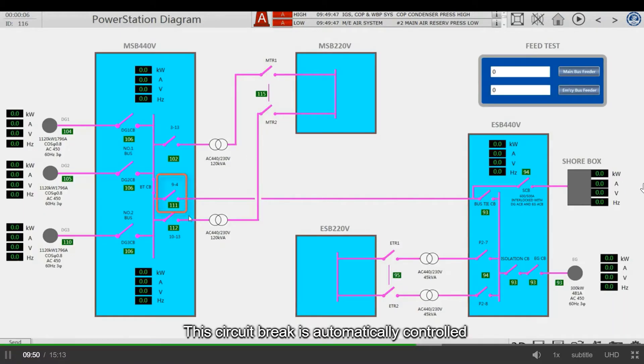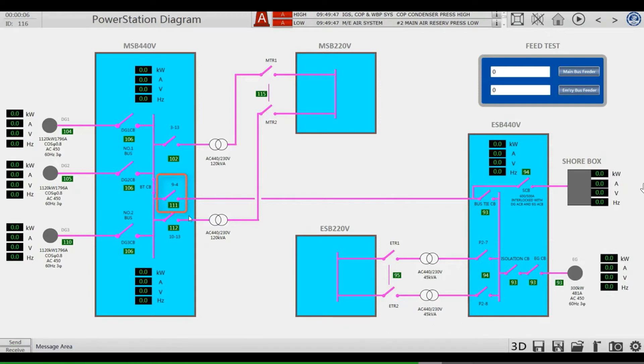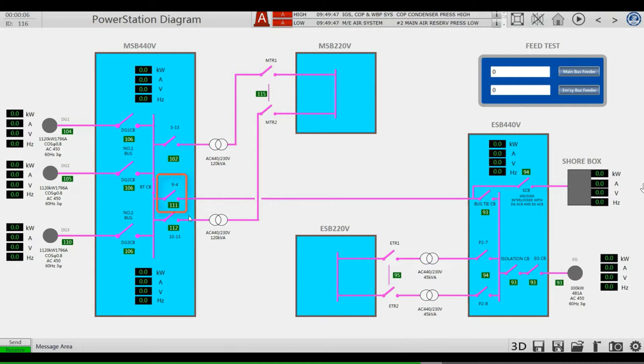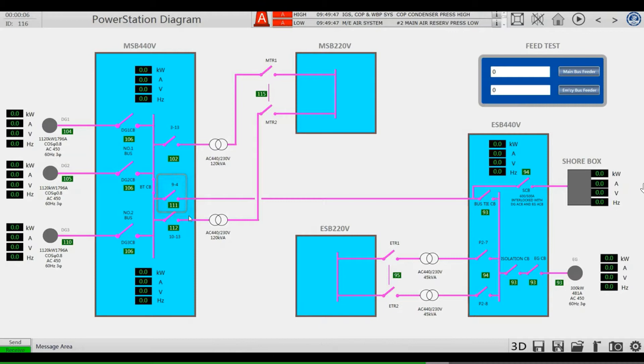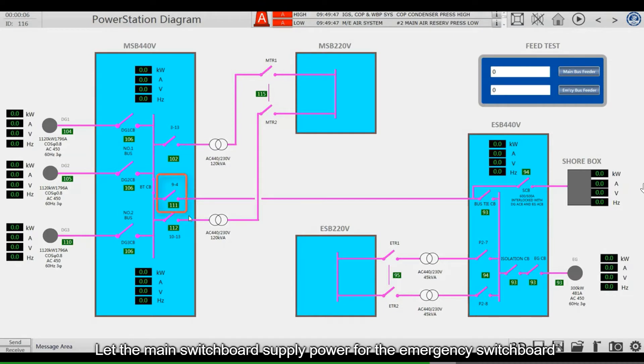This circuit breaker is automatically controlled. If the main switchboard loses power, the bus-tie circuit breaker should be opened. If the main switchboard has power, the bus-tie circuit breaker should be closed, letting the main switchboard supply power to the emergency switchboard.